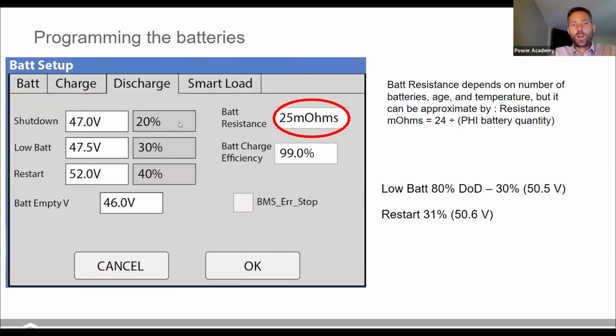So if you're running off of solar, you don't have a generator, utilities are down, it's nighttime, there's no more solar, the battery starts draining down. Once you get to 20%, it'll actually shut the loads off in the house. So keep in mind, if you want a lot of longevity with your batteries, you might want to be as high as 20%. But if you're only cycling your batteries occasionally, you can drop this all the way down to 0% and make full use of your batteries. I'll typically recommend 10% or 20%, depending on how often the batteries are cycled. If they're cycled daily, I recommend 20% because you get almost double the number of cycles.